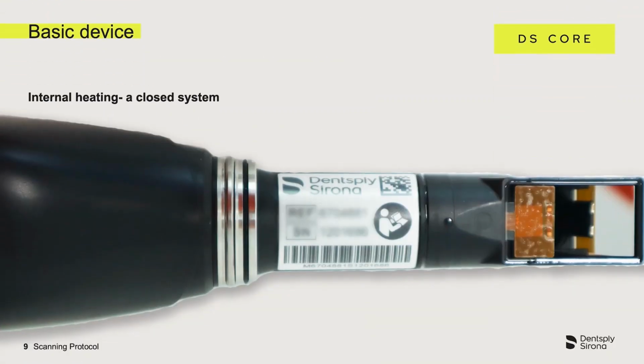The prime scan is designed as a completely closed system. This means that we also have an internal heater that protects the scanning glass from fogging and moisture ingress, but at the same time it is sealed so that we have no ingress of liquids during disinfection procedures. The sleeve completely covers this system and allows it to be used on the patient.